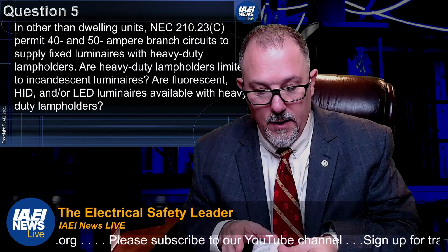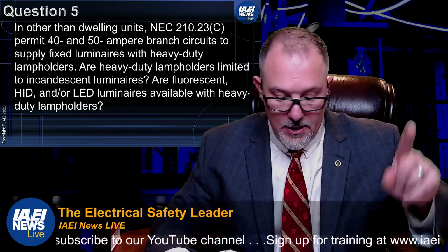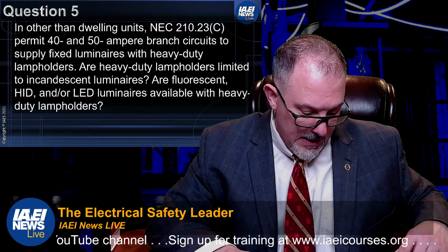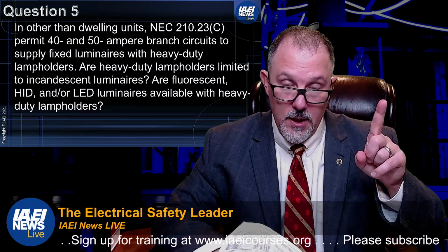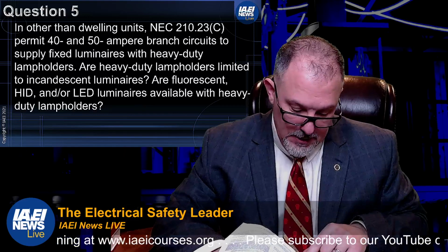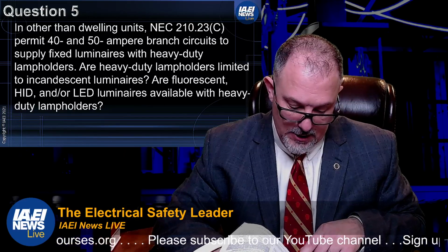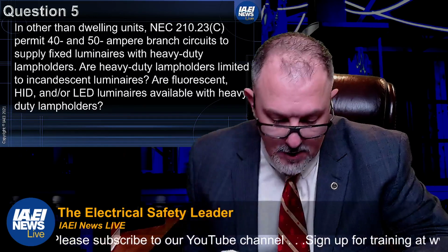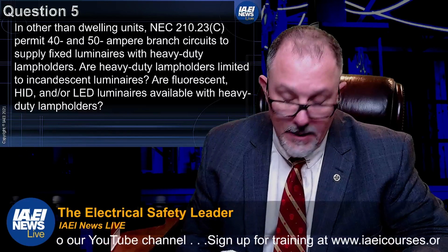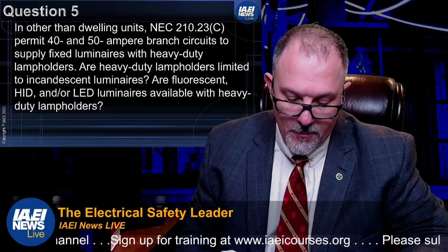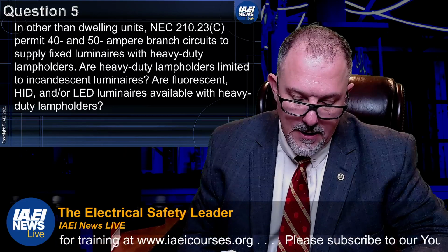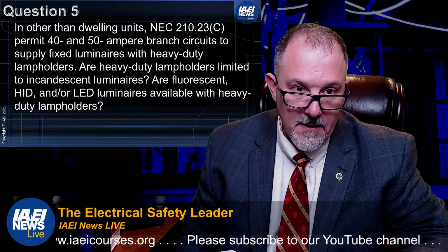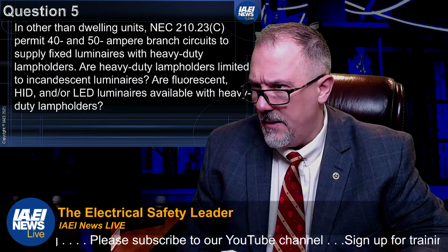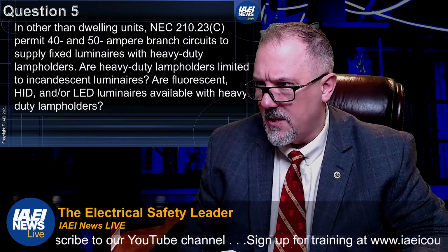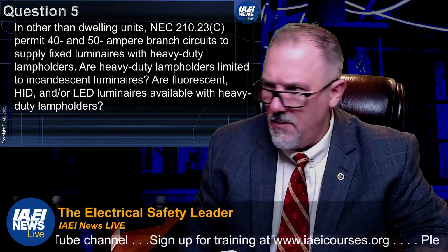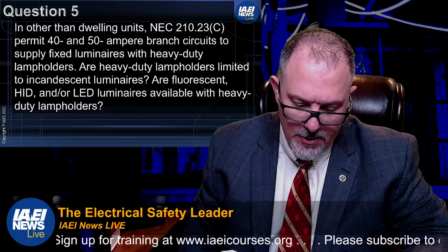What does 210.23 say? Where is 210? We know it is branch circuits, right? 210.23 is permissible loads. 210.23 just happens to be in Part 2 of Article 210, which is titled Branch Circuit Ratings. So 210.22, permissible loads, an individual branch circuit, it can supply any load for which it is rated, but in no case can it exceed the branch circuit ampere rating. All right, so that's basically what it says, and it says permits 40 and 50 branch circuits to supply fixed luminaires with heavy-duty lamp holders. Well, I'm sorry, I read 210.22.